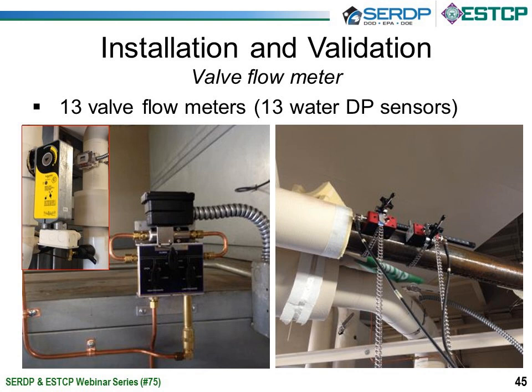Okay, the other type of flow meter for the water side is the valve flow meter. We take the same approach. We apply it to the valves. We've installed 13 of these, 1 on each of the chilled water supply valves to an air handling unit. We use an ultrasonic meter shown in the right-hand picture during the training process to provide the actual flow rate through that. We consider that ground truth coming in.